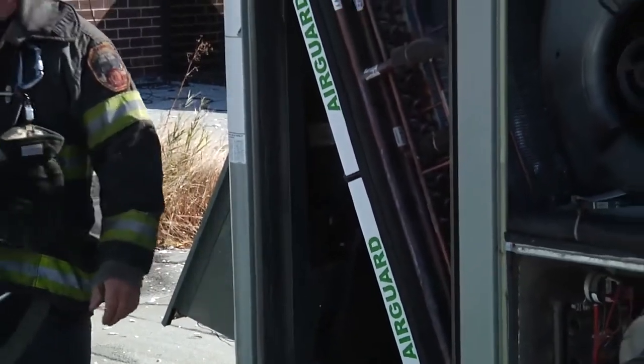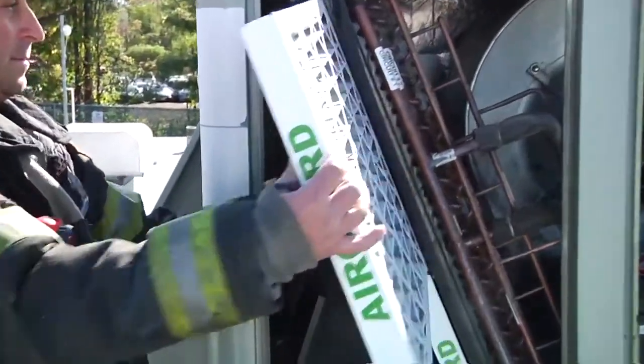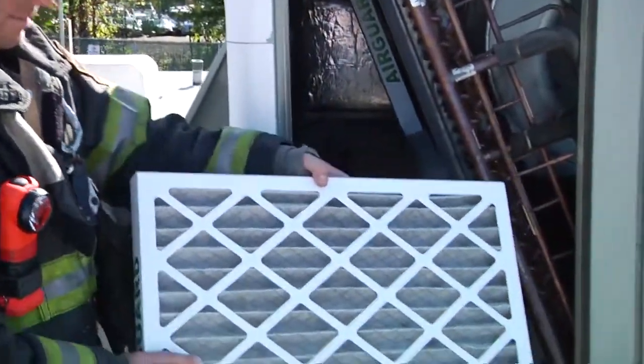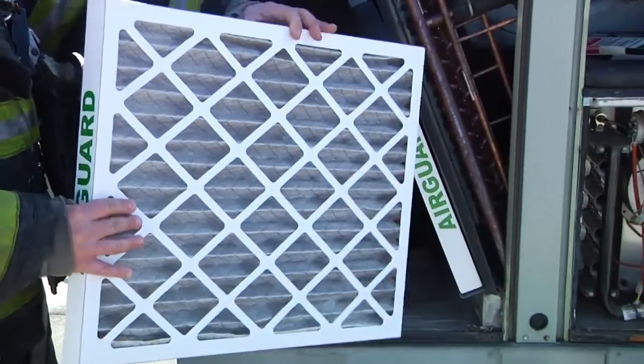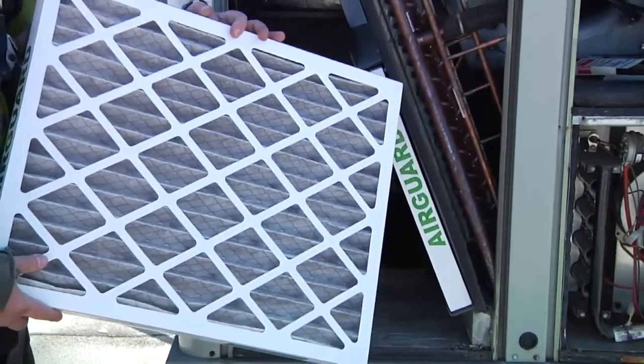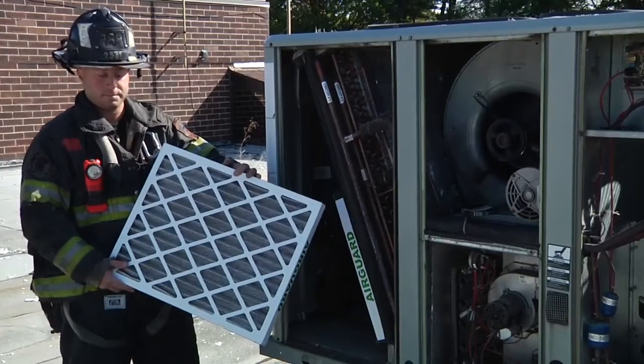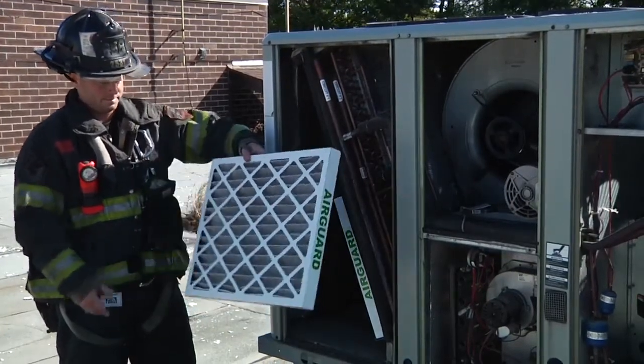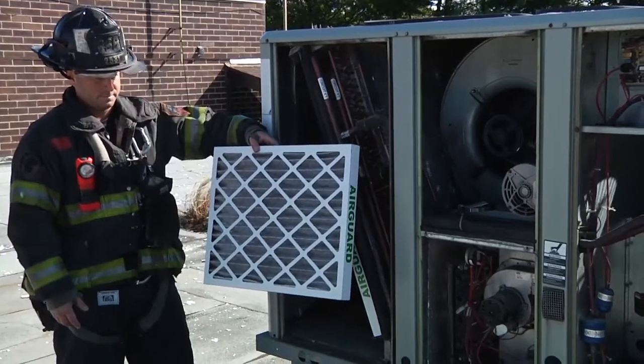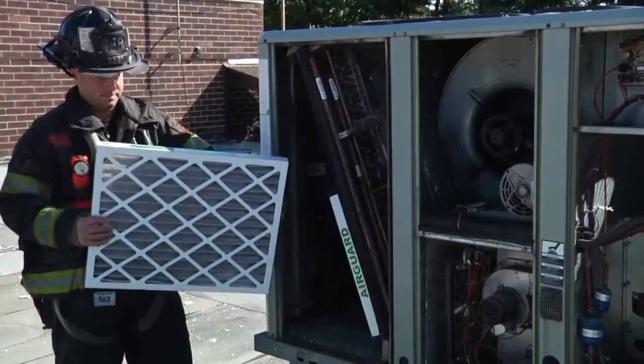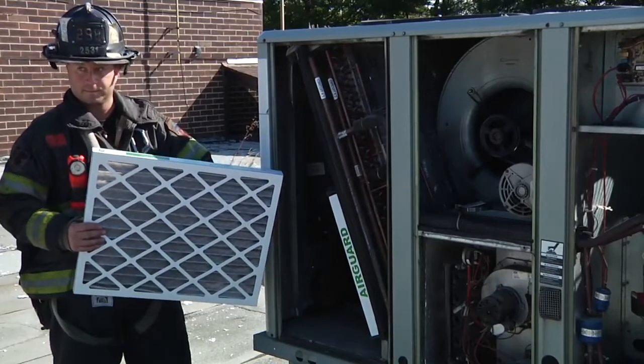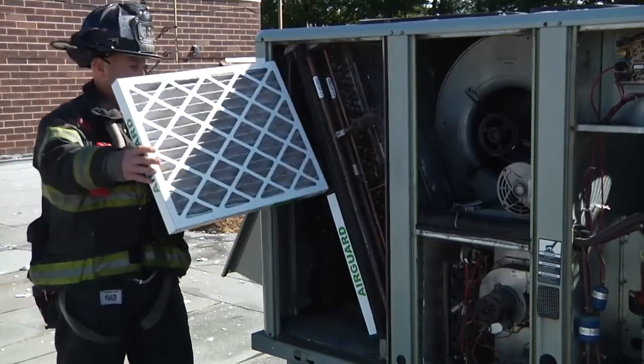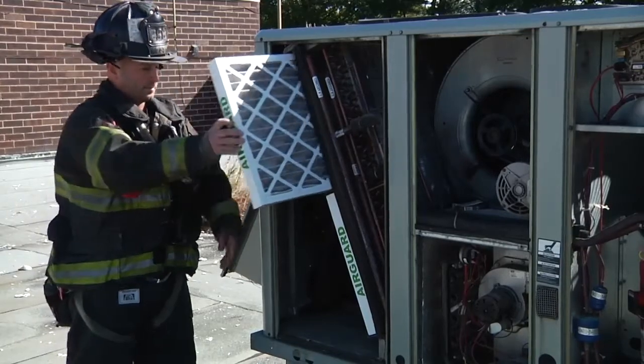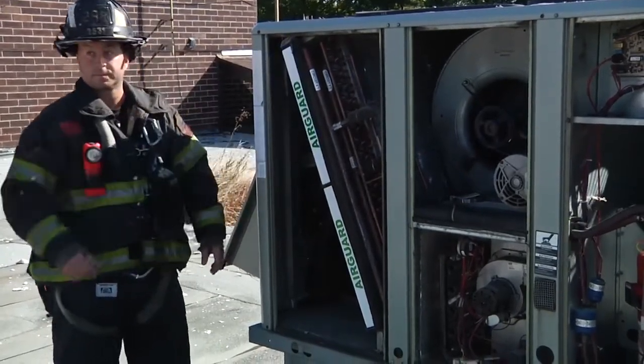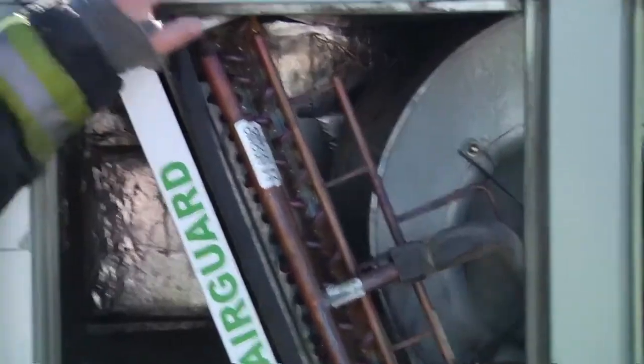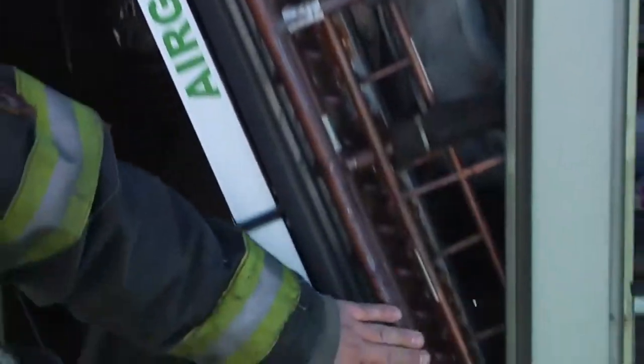we have the air filters. It might seem like a very simple component, but it's something that is overlooked all the time. I've been up and investigated rooftop units where that filter is original to the rooftop unit, which is 15 years old and hasn't been cleaned. If that is the case, it's going to create a mess on downstream components, and it's going to collect dust on the motor and cause the motor to burn out, and again, activate the 911 system when it's not really necessary. The next portion is the evaporator and the evaporator coils.